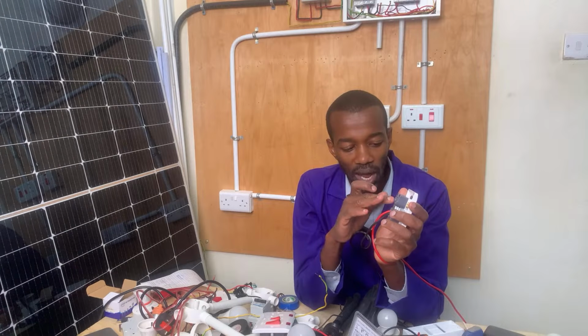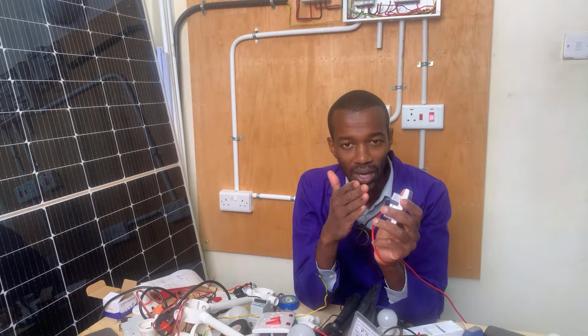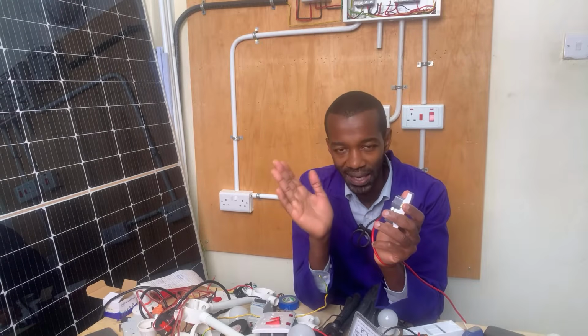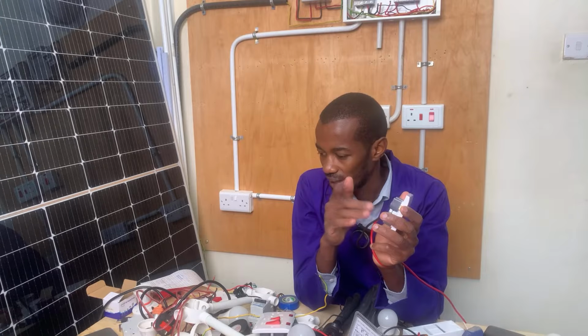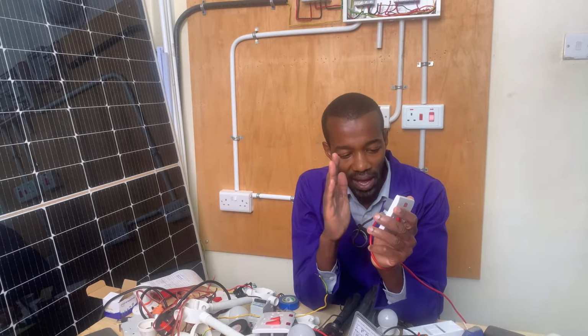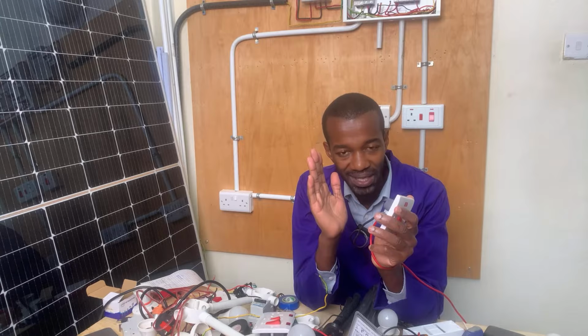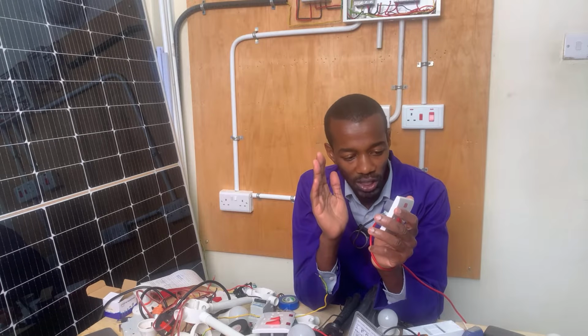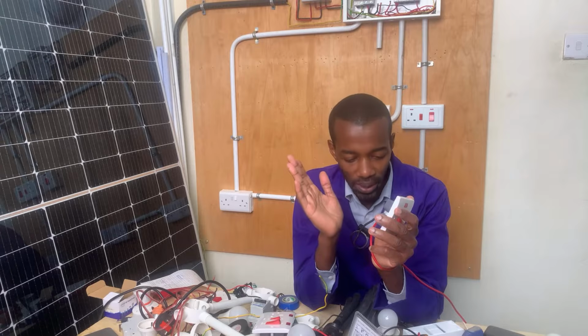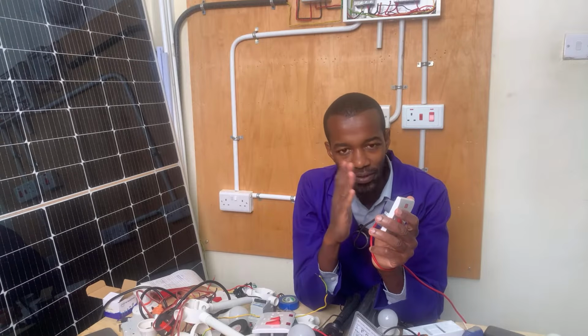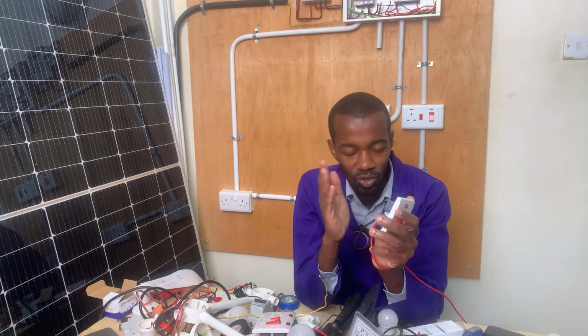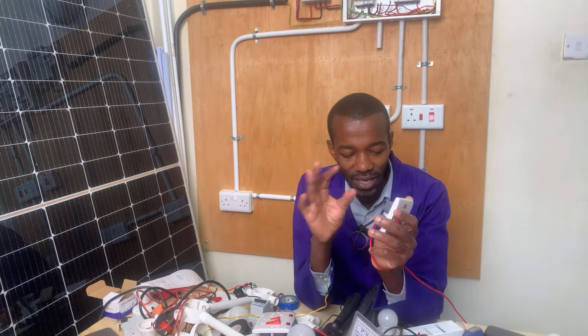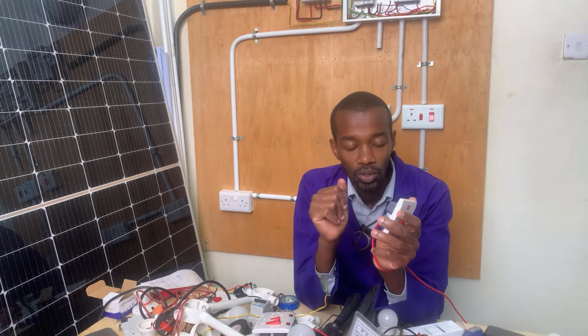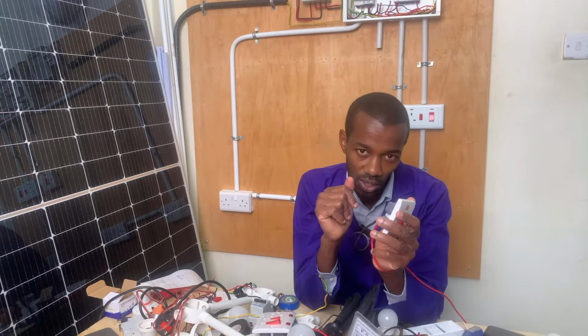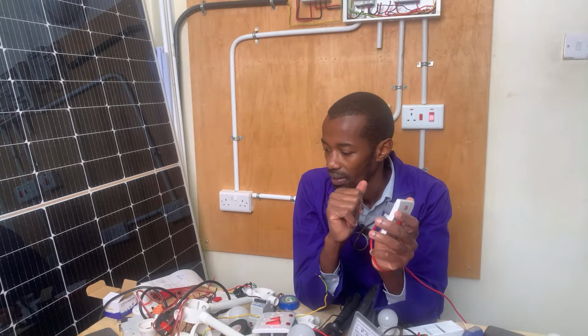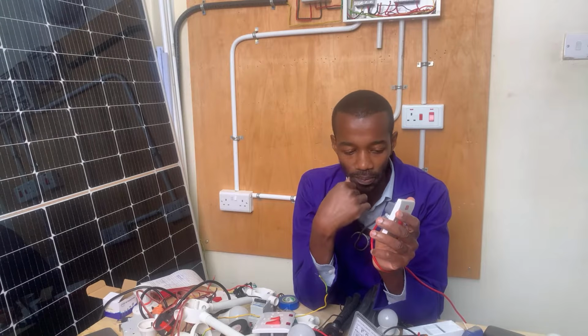So you're supposed to have the neutral and earth connection clearly separated, so that in the switch the earth connection is independent as it should be, and the neutral connection is independent as it should be. Just as we keep the neutral and the line very independent and clearly separated, we should also do that for the neutral and the earth connection, isn't it, my top boss?